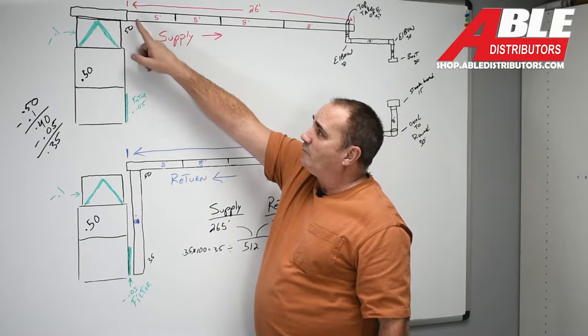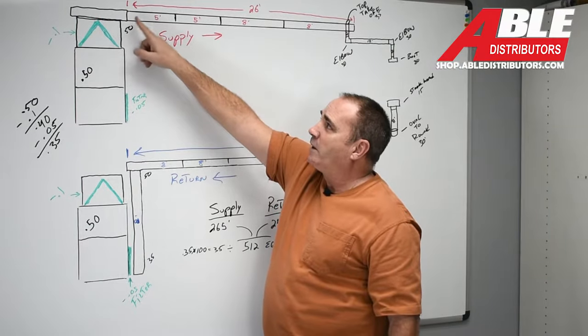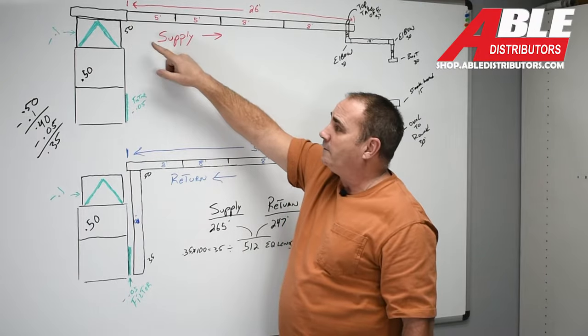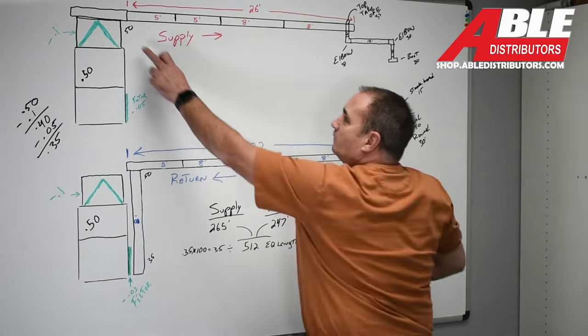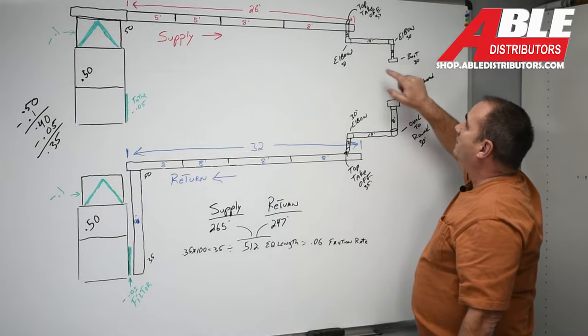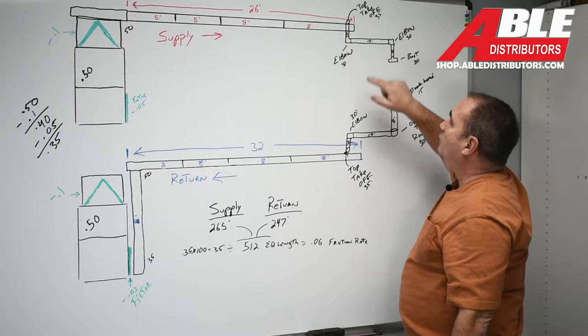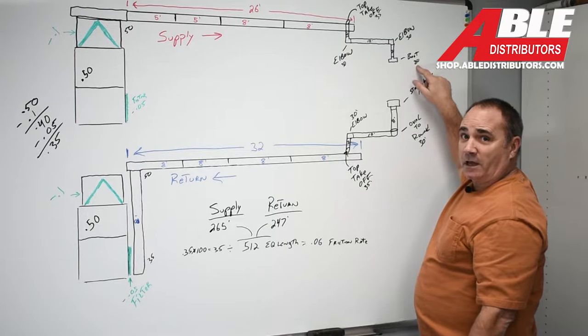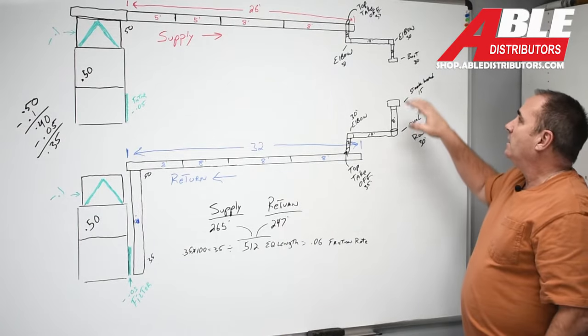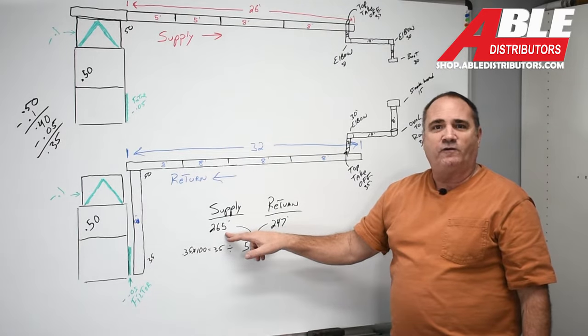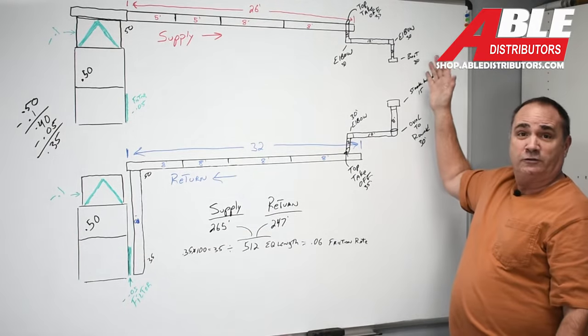The change of direction of this air from the plenum to the ductwork, that's equivalent to 50 feet of duct. So we've got 50 and 26. Every elbow is 30 feet. A top takeoff is 35. Add in the length of pipe. The boot is 80, believe it or not, a 4 by 10 floor boot.